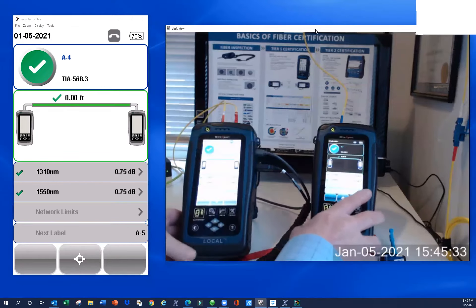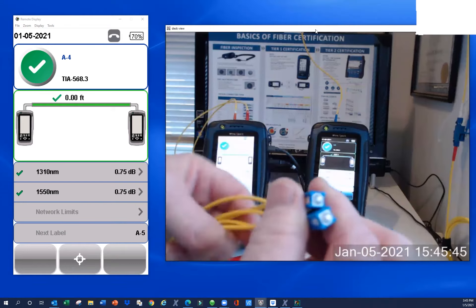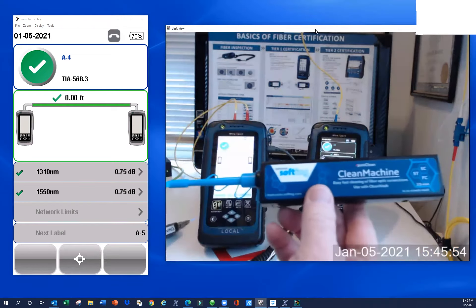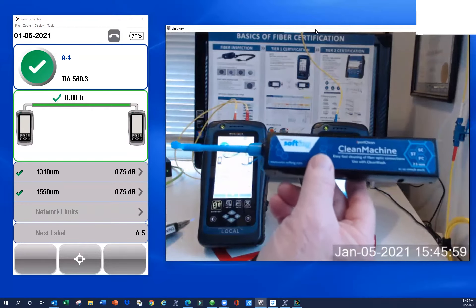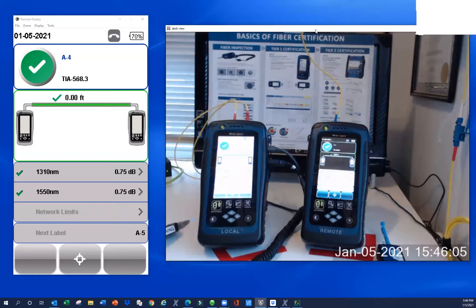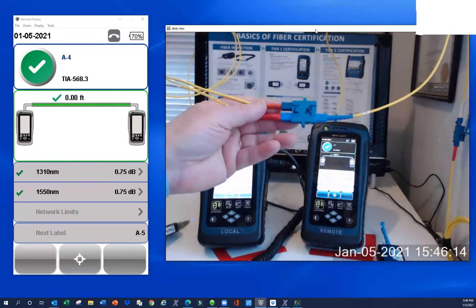So what are we going to need to perform a two-jumper set reference? First, we're going to need reference grade test reference cords — four SC to SC with the 2.5 millimeter ferrules. We're also going to need a cleaning product; this is Softing's CleanMachine, our version of the OneClick. Depending on how dirty your end faces are, you might also need wet cleaning. We're also going to need a duplex coupler — SC, with four SC connections.